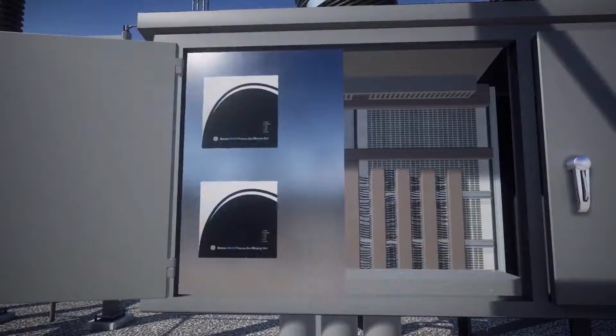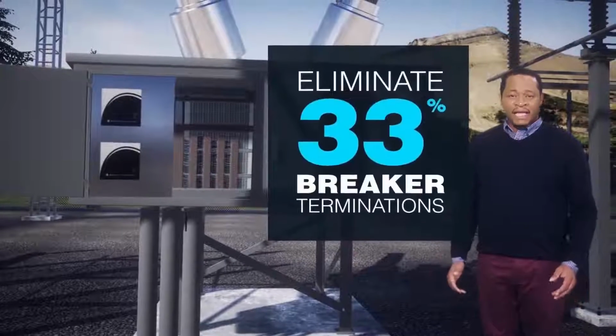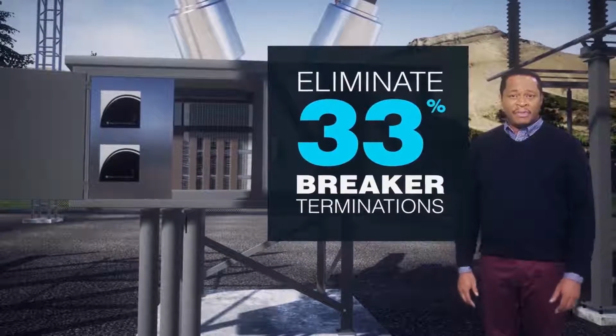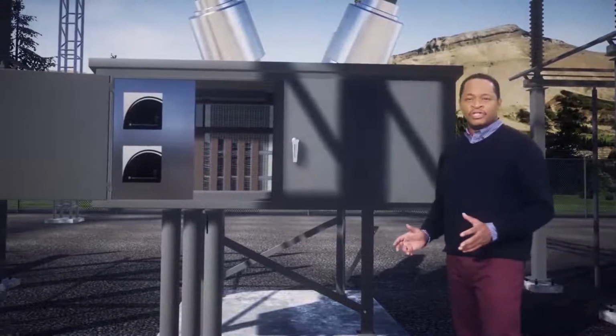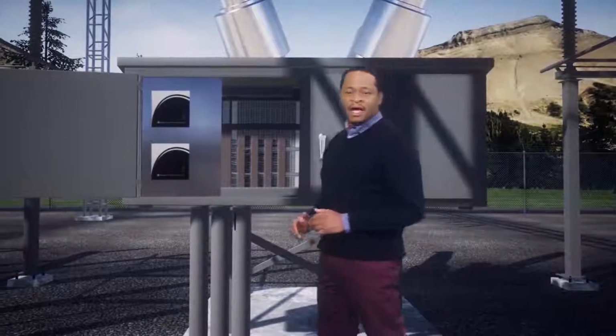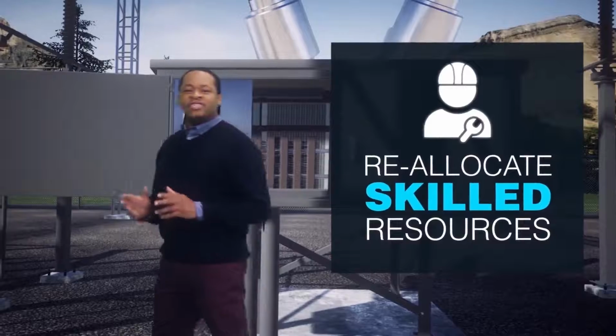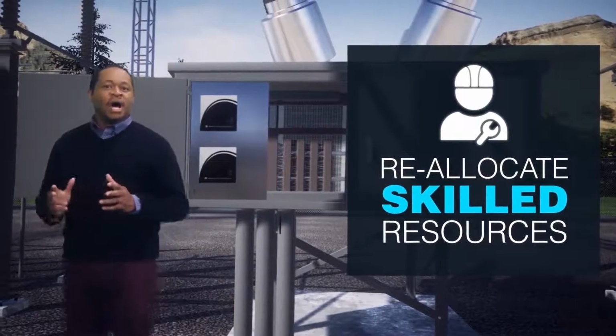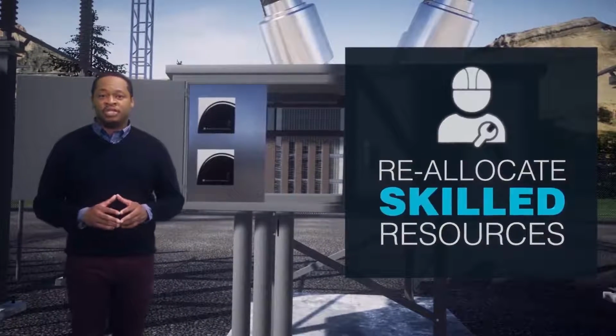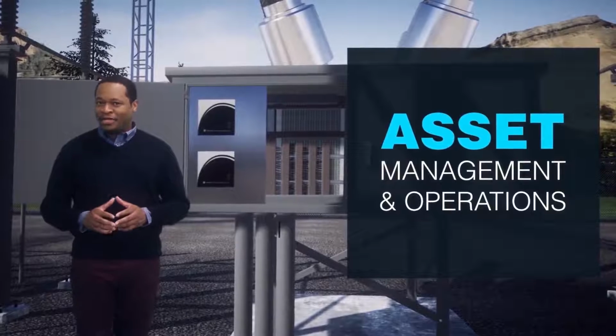What a difference. Very clean and simple, right? And definitely safer than having direct access to the high voltage terminals we saw before. By eliminating up to 33% of breaker terminations, we're able to move resources away from designing and maintaining copper wires. Instead, these skilled resources can be allocated to other critical aspects of the substation, like asset management and operations.